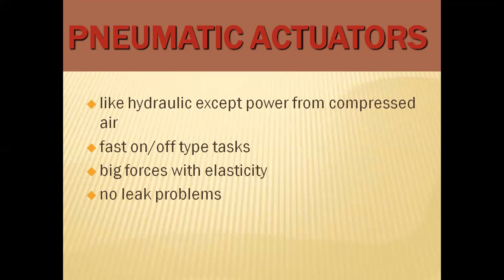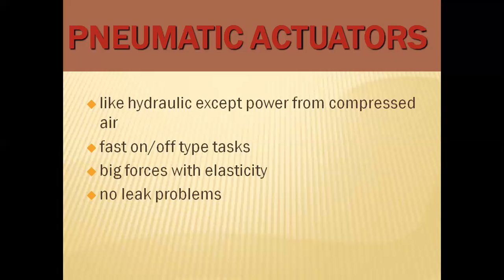Considering pneumatic actuators compared to hydraulic, pneumatic systems generate quick actions — either switching on or off very fast, with drastic and quick movement, and can extend with large forces and elasticity. There will not be any leakage problems, because if any leakage occurs, the air tends to escape to the atmosphere. Hence, there will not be any hazardous situations in the case of pneumatic actuators.